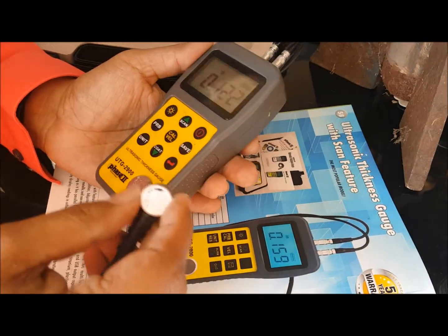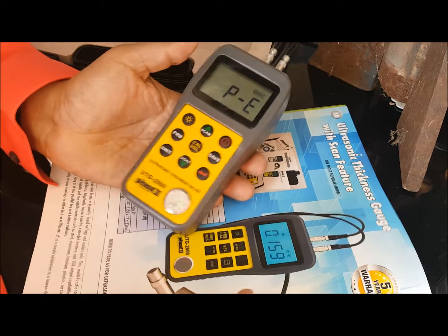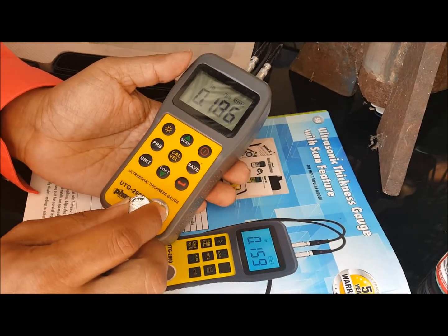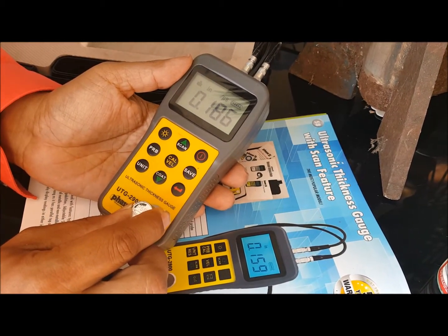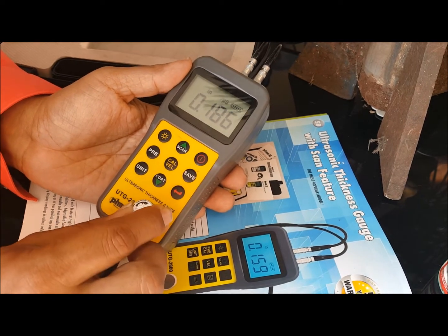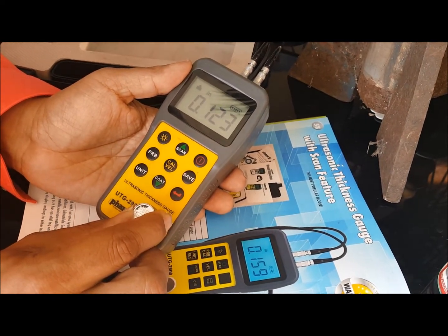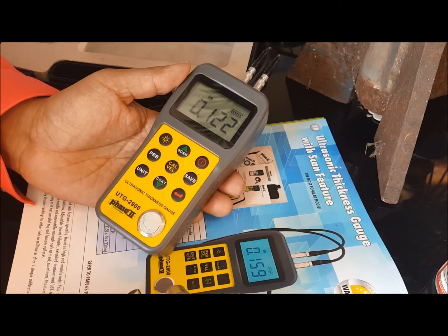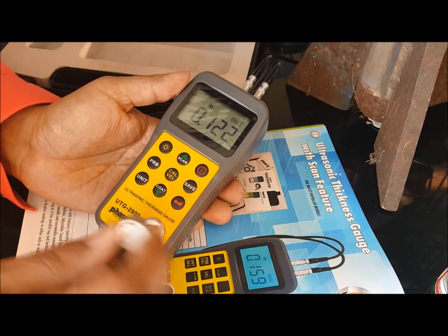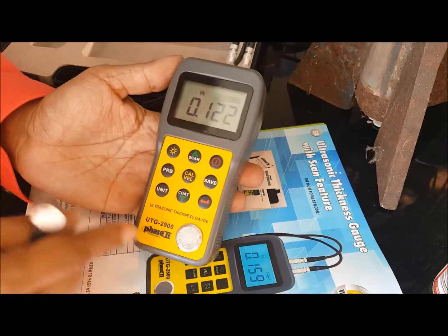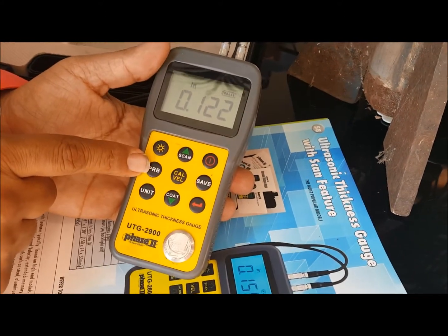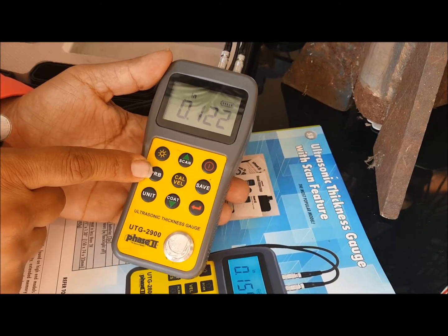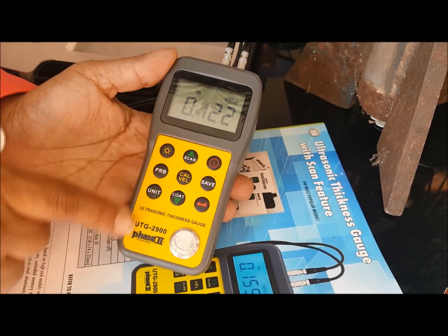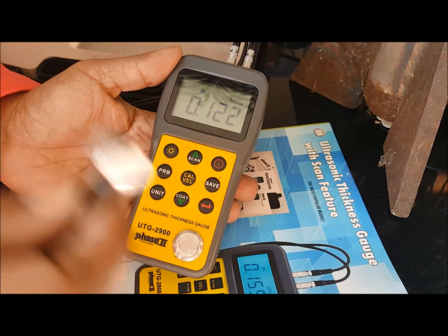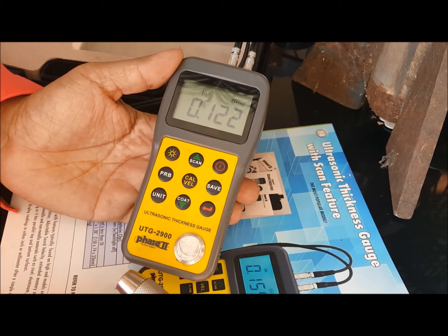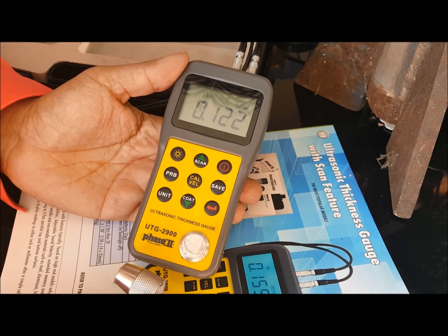The first thing I'm going to do, after we turn it on, is make sure it's reading accurately. So we got there, that's fine. This block is 0.123, 0.124 actually, so this is fine. You can see it has a probe zero, the equivalent of zeroing out your caliper. This particular 2900 reads through coating, if you have coating on your material, your pipe, or your piece of metal.